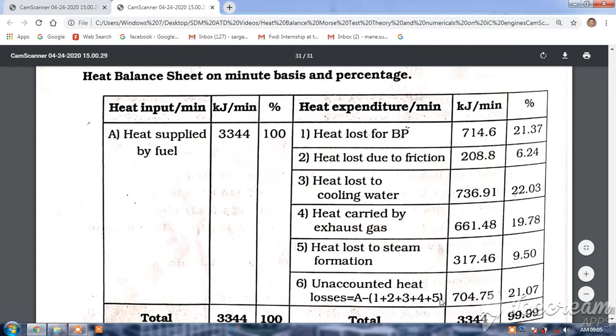How you get percentage: 714 divided by 3344 × 100 = 21%. Similarly, 208 divided by 3344 × 100 = 6.24%. This is how we calculate all heat balance percentages. The heat should be balanced - whatever is supplied on the left side equals the total expenditure.